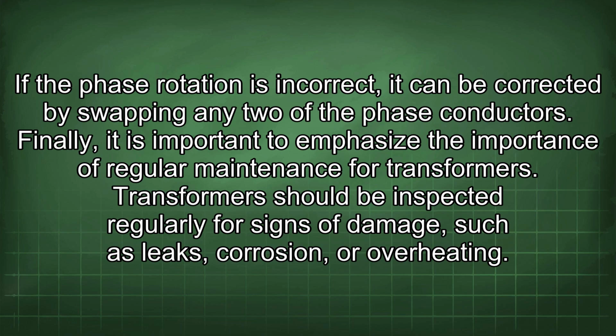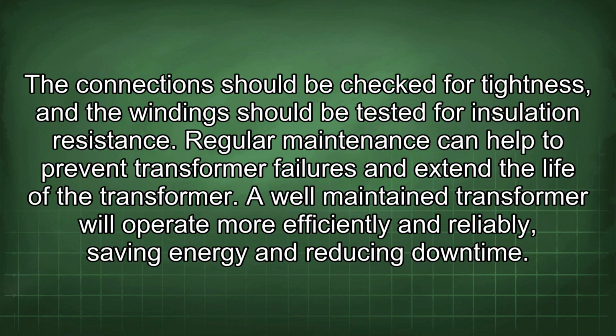Transformers should be inspected regularly for signs of damage, such as leaks, corrosion, or overheating. The connection should be checked for tightness, and the windings should be tested for insulation resistance. Regular maintenance can help to prevent transformer failures and extend the life of the transformer. A well-maintained transformer will operate more efficiently and reliably, saving energy and reducing downtime.